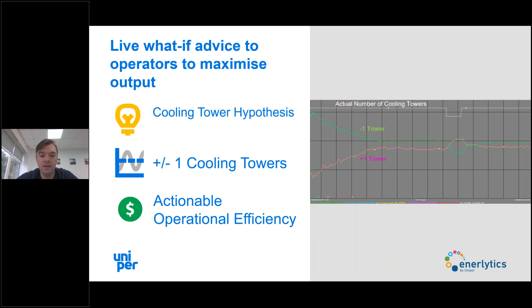So in this unit, it's around 4 megawatts, which is a tradable capacity in that market. So they could be getting that as either flexible payments or wholesale value. And to prove that it works, you can see here we took a cooling tower out, dropping it down to 1 minus, and then you can see here the system saying bring a cooling tower back in because it will improve your efficiency, and that's what happened, and it's returned to good operation. This is in the control room of the site now, and they take effective action on the number of cooling towers each morning, afternoon, day, based on the weather conditions.